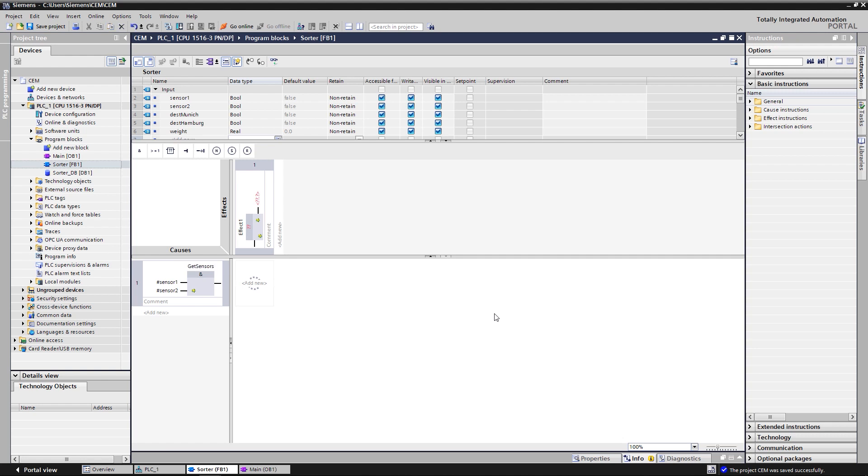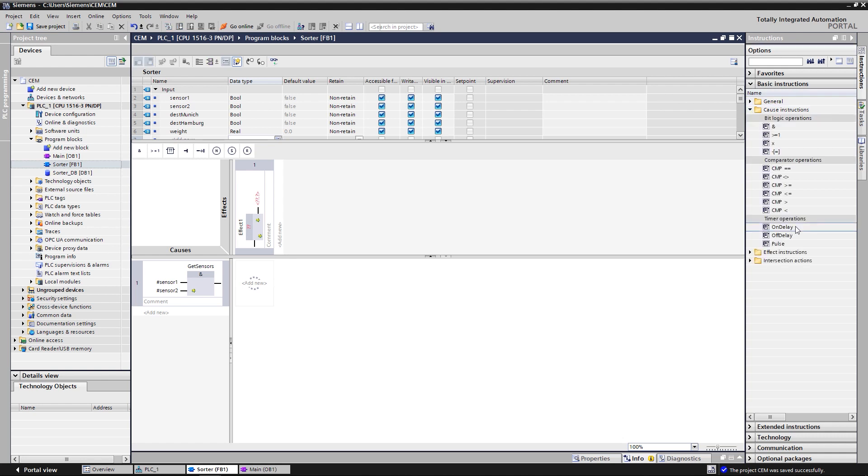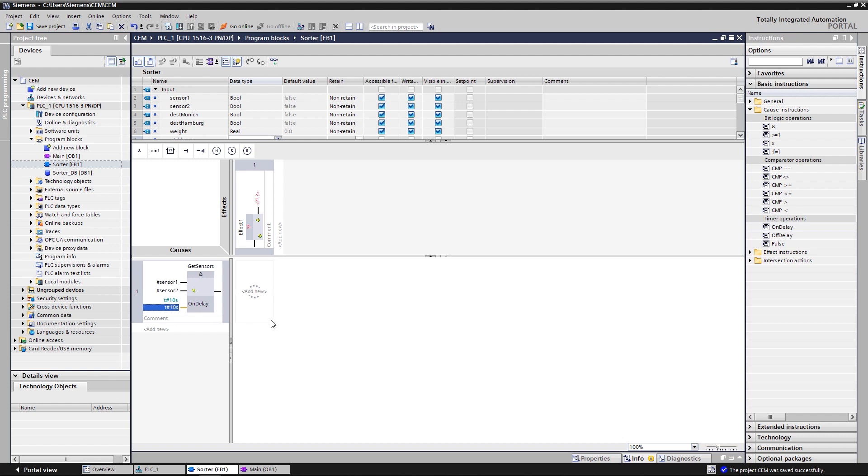Now we need a timer in the first cause, so that the cause only becomes active after the on-delay has remained. But how can you add a timer here? Well, it's really easy. The timer can be added simply by drag and drop. With this parameterization, the timer on delay delays the activation of the cause by 10 seconds. This timer is used to check whether the bag was on the belt for long enough to be weighed.